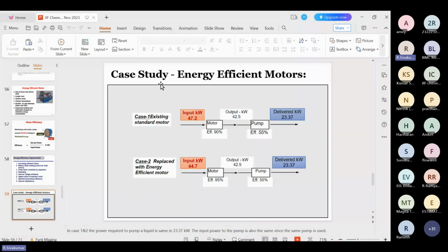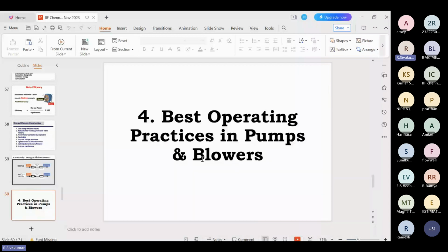If it is running for the furnace continuously, means this pump has to run 24 hours. So kindly put a better energy efficient motor here. You can save some here. One example: 47.2 to 44.7. This is the impact of the efficiency increase of the motor. And the final topic is best operating practices in pumps and blowers.